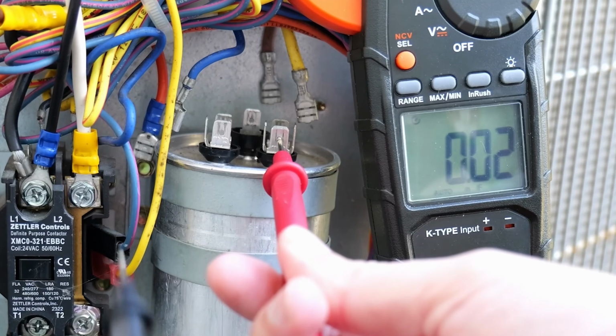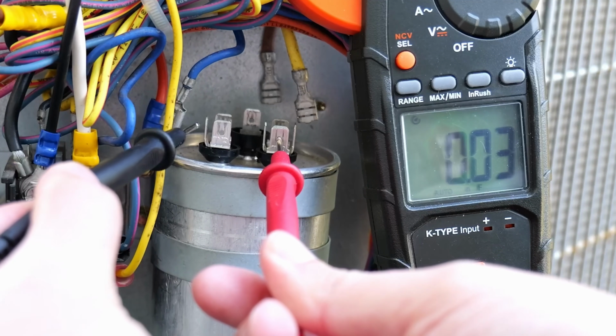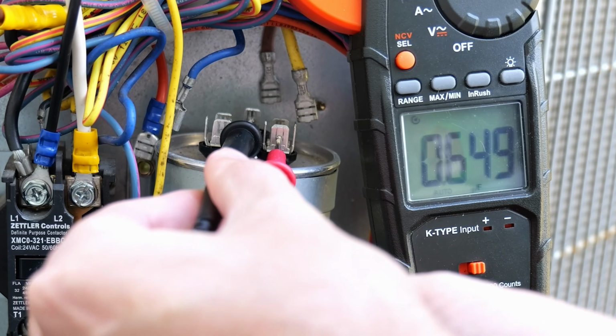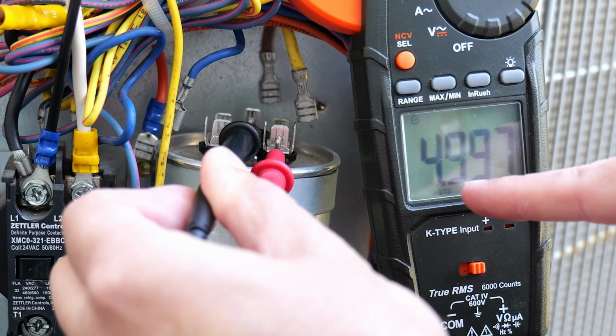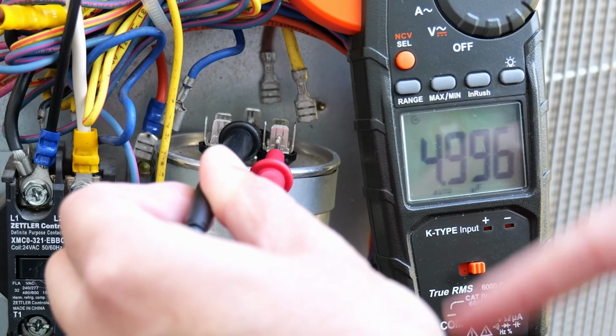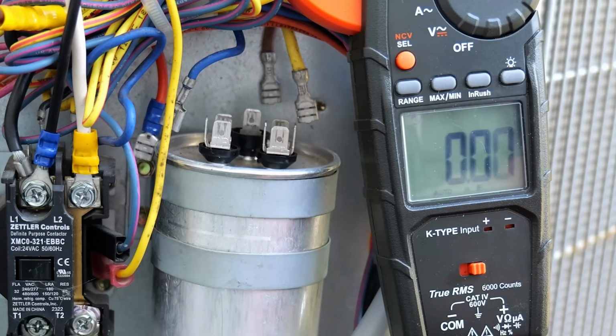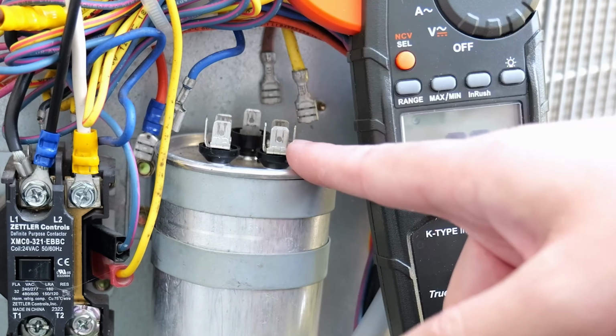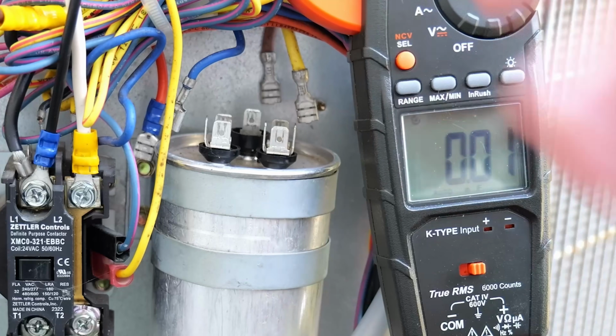So I'm going to keep that one probe on my common, take my second probe off of the herm and move it over here to the fan and see what our reading is then. And as you can see, it's showing 4.997. So pretty much right at 5, which is what we want to see. So this capacitor is still in very good and working condition.